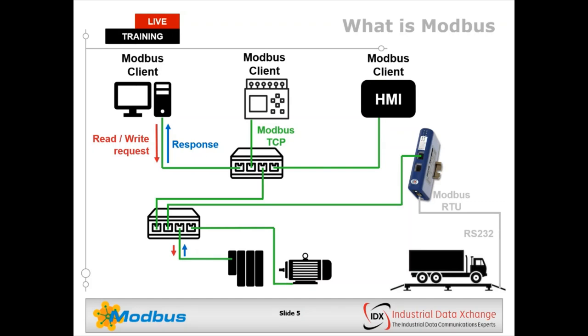Here I've highlighted a typical Modbus network, showing an integration between Modbus TCP, which is the Ethernet-based version of the protocol, and Modbus RTU, which is the serial-based version. We have what we call Modbus clients — these are the masters of the Modbus network. They ultimately control communication, reading information from low-level field sensors. Modbus is an application-layer messaging protocol designed to fetch and transfer information to and from remote devices.